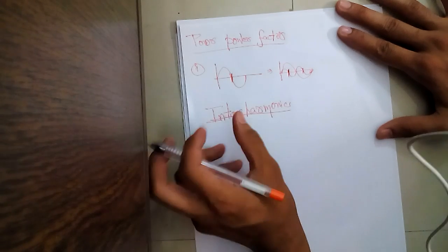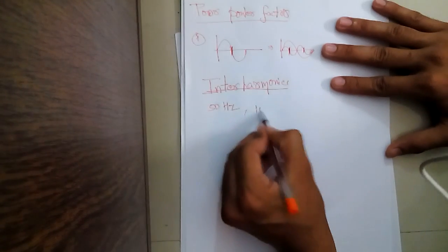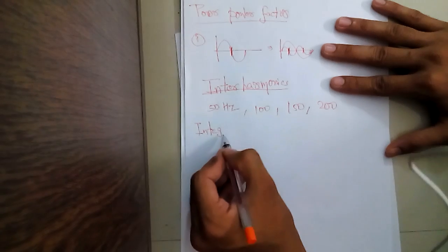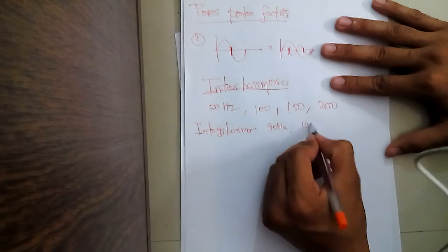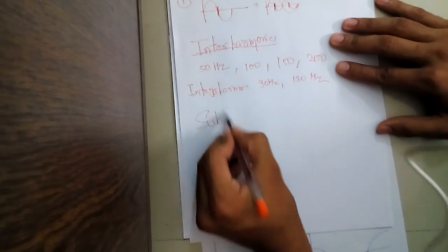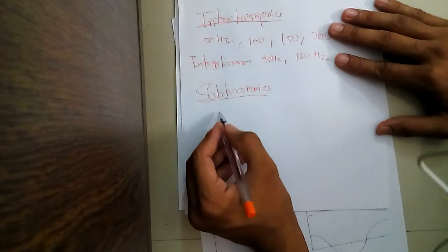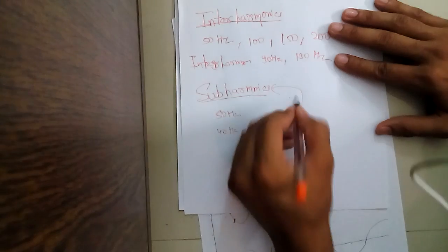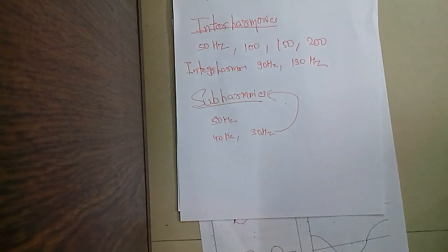Now two terms I would like to discuss: inter-harmonics and sub-harmonics. Inter-harmonics are frequencies which are in between the integral multiples of the fundamental frequency. Suppose my fundamental frequency is 50 Hz; the multiples are 100, 150, 200. So inter-harmonics would be 90 Hz, 130 Hz — frequencies in between those integral multiples. Sub-harmonics are frequencies lesser than the fundamental frequency. So if my fundamental frequency is 50 Hz, then 40 Hz or 30 Hz would be called sub-harmonics. This is the end of the first video; in the next video we will see the effect of even harmonics.